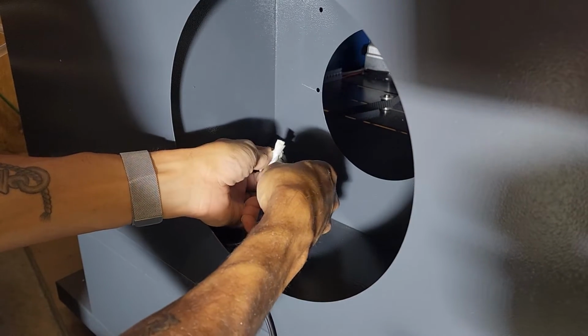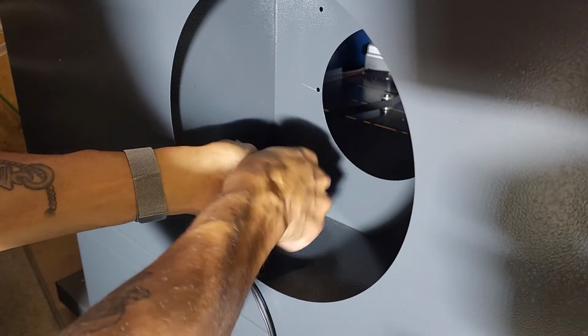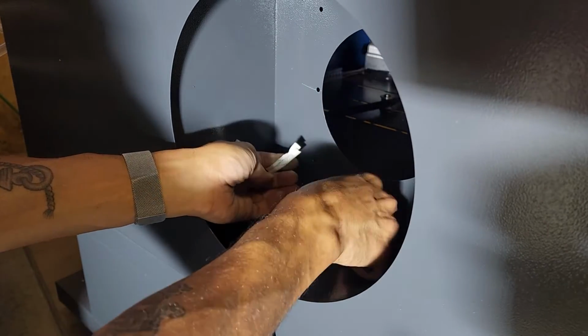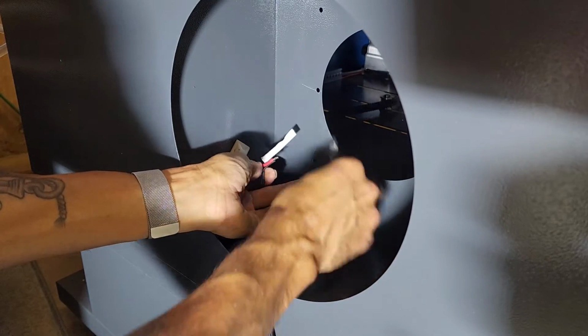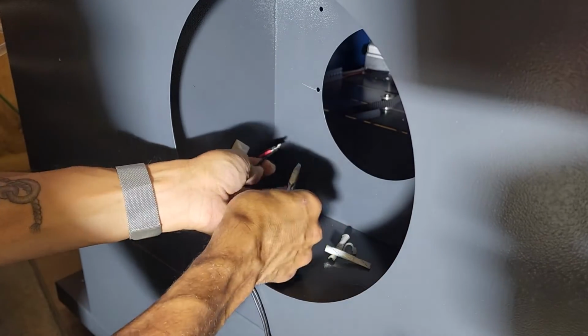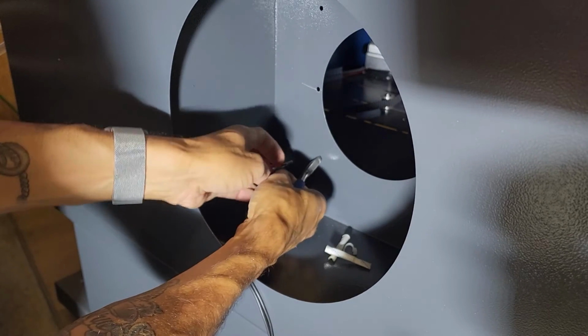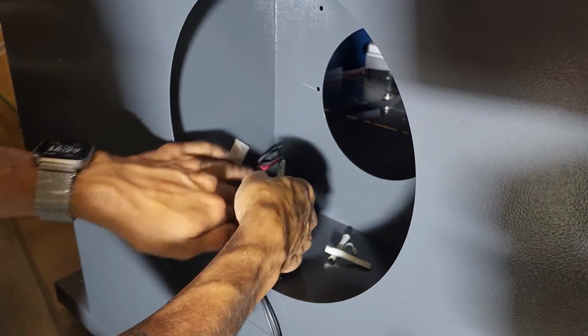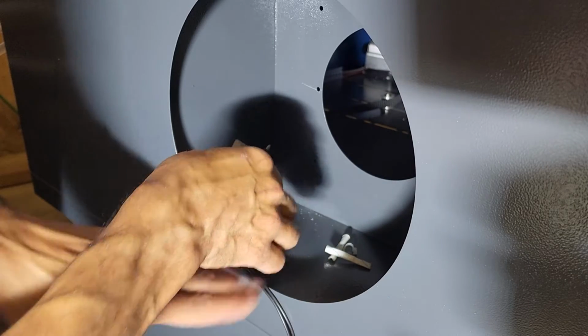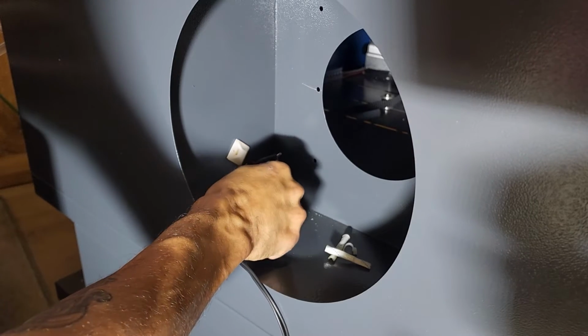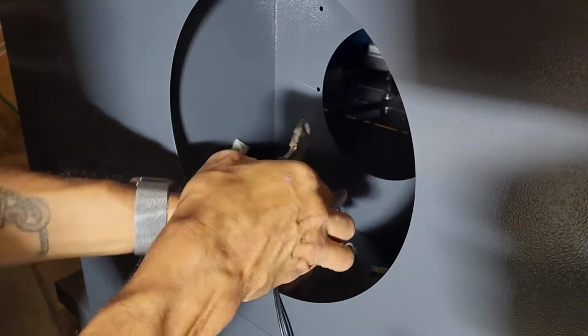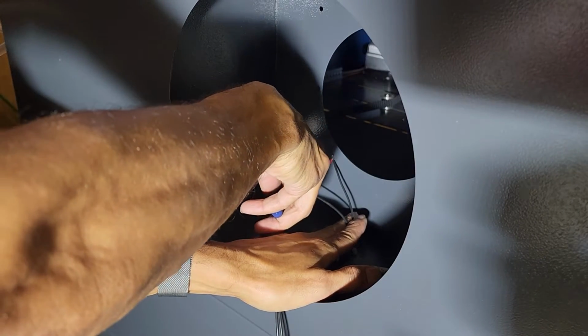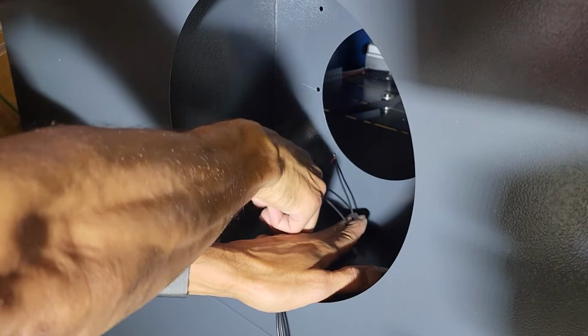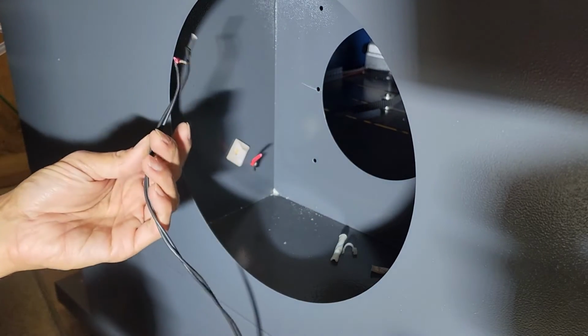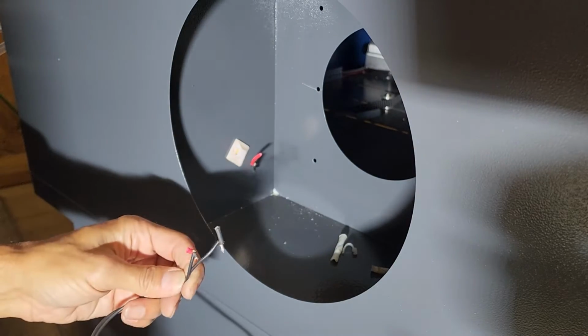I'm going to clip this off here. This is just some insulation they've put over these connections to keep everything from shorting out. Cut the wires one at a time—if you cut them both and there's residual power, which there shouldn't be, there's no sense in teasing the tiger. Cutting them one at a time makes arcing a lot less likely. I'm using insulated tools here, and to be extra safe, you could wear gloves as well.